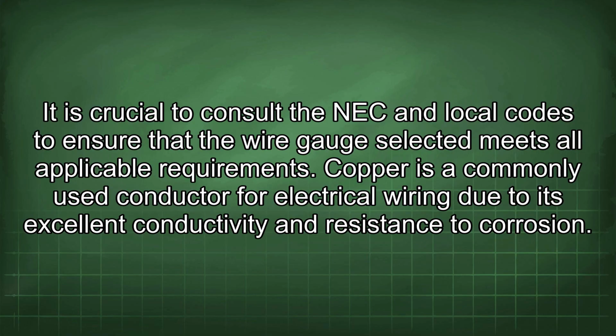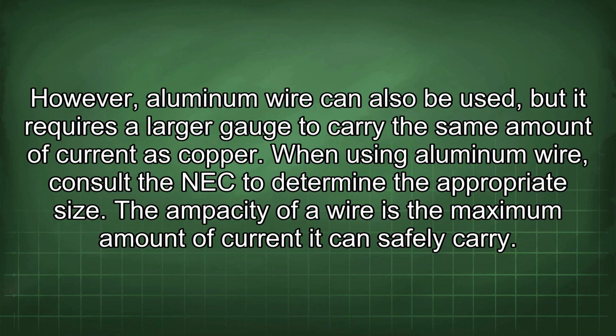requirements. Copper is a commonly used conductor for electrical wiring due to its excellent conductivity and resistance to corrosion. However, aluminum wire can also be used, but it requires a larger gauge to carry the same amount of current as copper. When using aluminum wire, consult the NEC to determine the appropriate size.